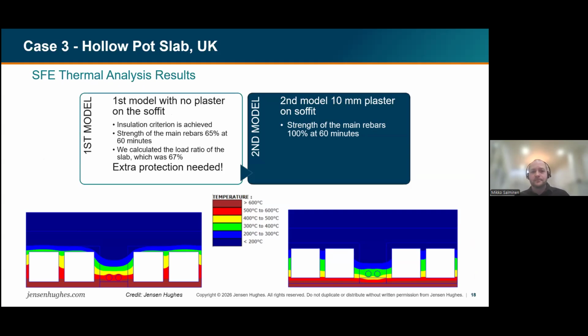So the first model, we concluded that yes, we can achieve the insulation criteria, but the strength of the main rebars is only 65% of the normal temperature value at 1 hour. And based on the structural calculations, we needed 67%. So it was quite close. But of course, with the existing structure, we also want to have some safety margin. So we concluded that in this case, the 10 millimeter plaster is needed below the structure to limit the rebar temperatures. And with that, the strength of the main rebars was a full 100% of the normal temperature strength at 60 minutes. So it was a clear solution for this case.